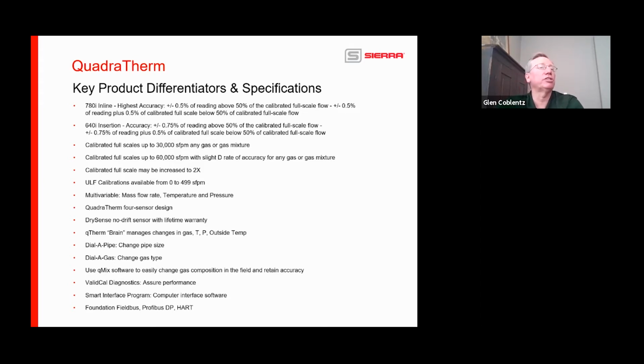So very, very low flow rates, and this can be done for 640i or 780i. And then when the order gets sent in, if you have a full scale on there that actually is a ULF calibration, John or Fred will send it back to you going, well, your full scale flow rate's equivalent of 350 standard feet per minute. Would you like to add the ULF, or would you like to round up to 500 standard feet per minute so you don't have to pay that adder? So we'll give you that option to do that. Even if you round up to 500, remember the accuracy statement still applies. You're still going to be measured all the way down to 0.